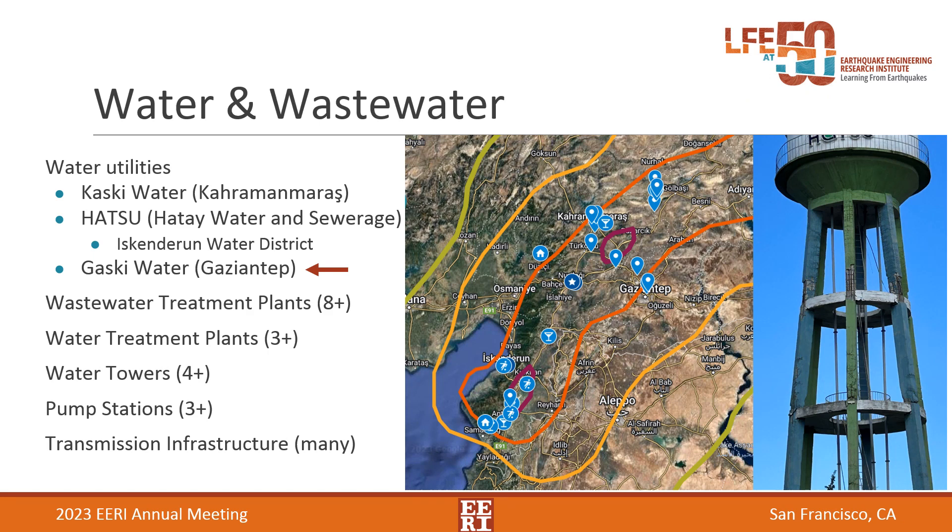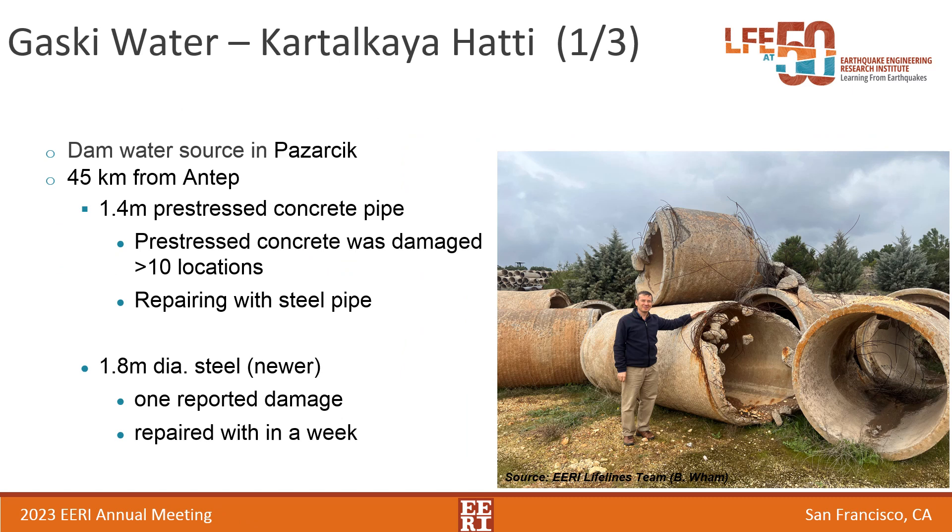I'll provide some background on water and wastewater infrastructure. We looked at many different systems — treatment plants for water and wastewater, towers, pump stations, and transmission infrastructure — and talked to a number of water utilities. Kaski water, for instance, had performed 5,000 pipe repairs by the time we arrived, which is about 120 repairs a day. Hatsu was heavily damaged in the Antakya area and is still unable to provide water; they're pumping three times the normal amount but can't access many pipe breaks because they're under damaged buildings. I'll focus on Gaski water, where we have specific examples of damage.